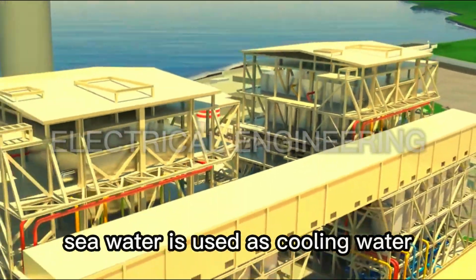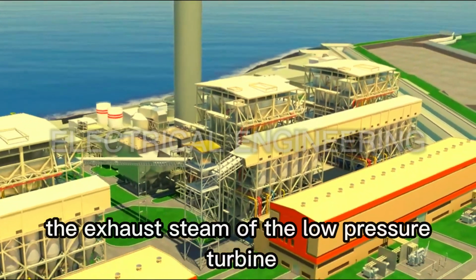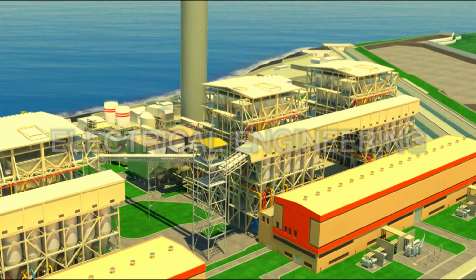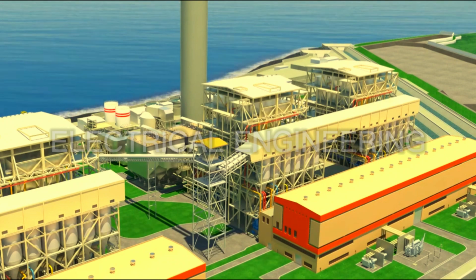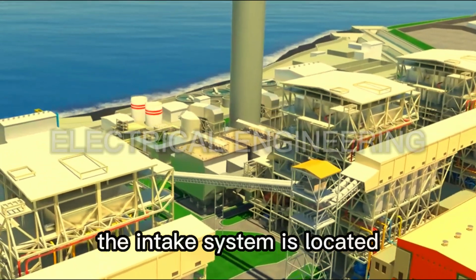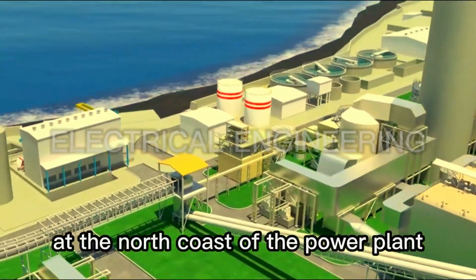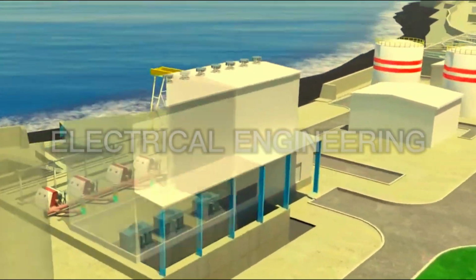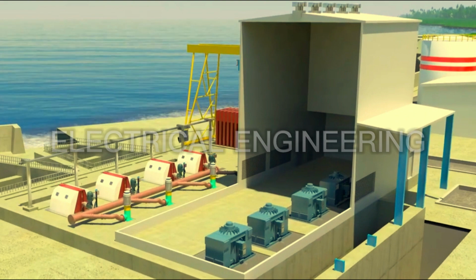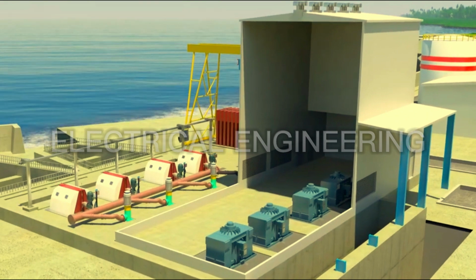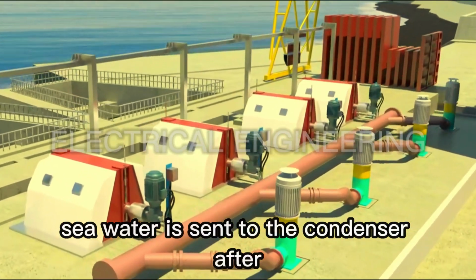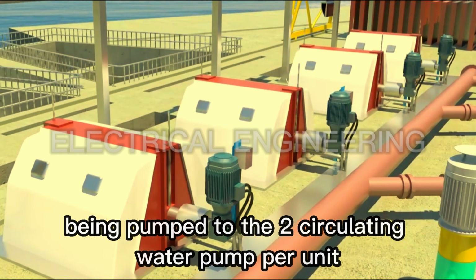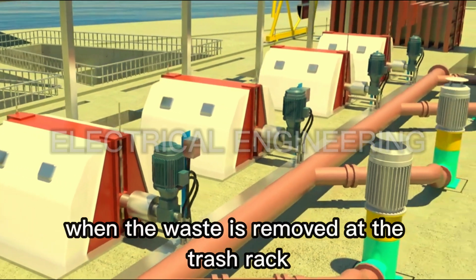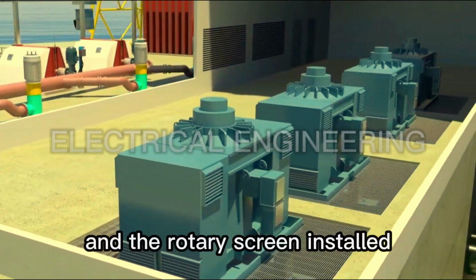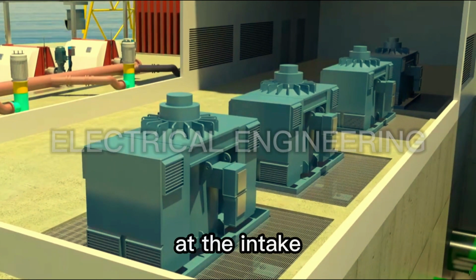Seawater is used as cooling water in order to drain the exhaust steam of the low-pressure turbine. For this purpose, the intake system is located at the north coast of the power plant. Seawater is sent to the condenser after being pumped by the circulating water pump per unit when the waste is removed at the trash rack and the rotary screen installed at the intake.